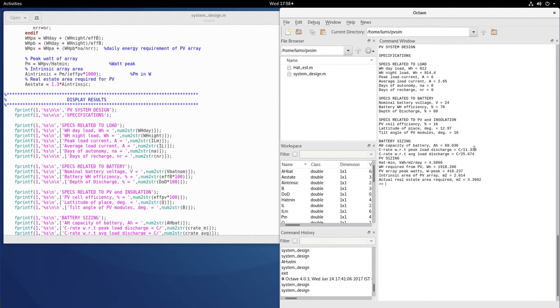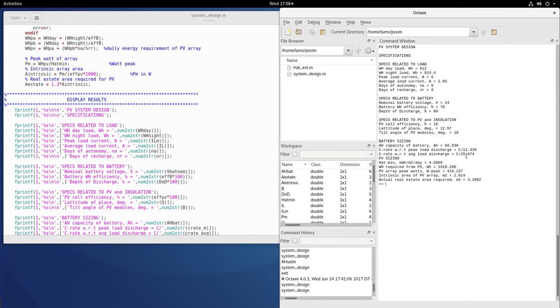For PV sizing, HAT minimum is 4.58 kilowatt-hours per meter squared per day. The peak watts for the PV array is 418 W, intrinsic area is 2.6 m², and actual real estate area is around 3.4 m², just as we calculated manually.